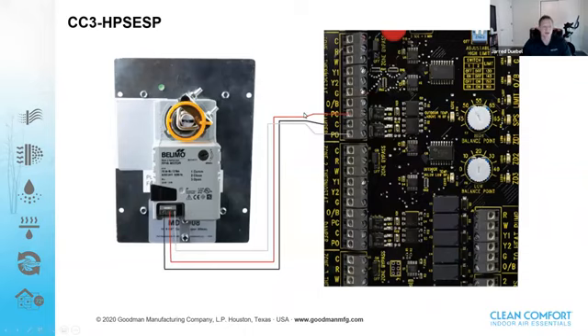Okay, now a little bit more of a close-up on the damper. We'll go over some of the specs on the dampers in just a moment. But first of all, I often get questions on how many dampers we can put on a specific zone. Well, it comes down to the transformer. We offer a 40 VA transformer. When it comes to the stat and the zone control panel, they're only drawing a little bit of power there, so you're going to get most of your VA draw coming from the dampers.